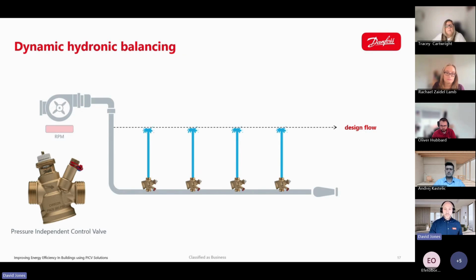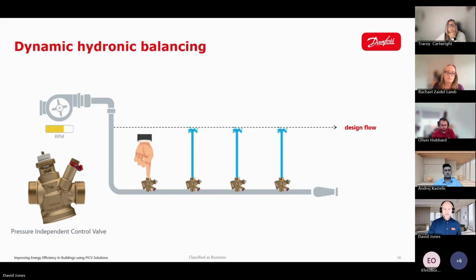So, proper hydronic balancing is achieved by dynamic hydronic balancing using pressure-independent control valves. Under partial load conditions, the flow through each valve remains consistent and at the set level of the valve. It doesn't increase or decrease as the pressure is spread evenly across the system and remains at the desired flow rates. As you can see, the modulating pump ramps down and is now running at a reduced speed as the excess flow of water isn't able to get through the PICV. This is also reducing the wear on the pump, as well as reducing the amount of power needed to get water around the system, increasing pump efficiency. So to reiterate that point once more, the only proper hydronic balancing is dynamic hydronic balancing using PICVs. By utilizing pressure-independent control valves, we're able to achieve perfect balancing at all loads.